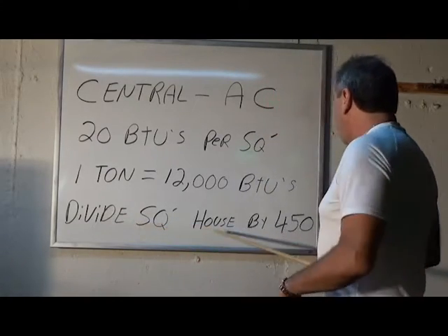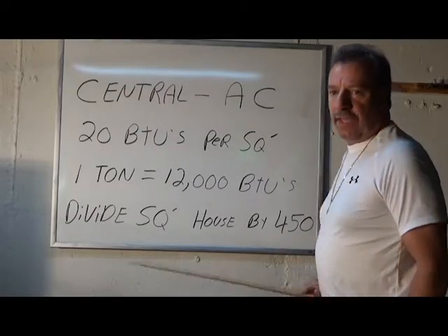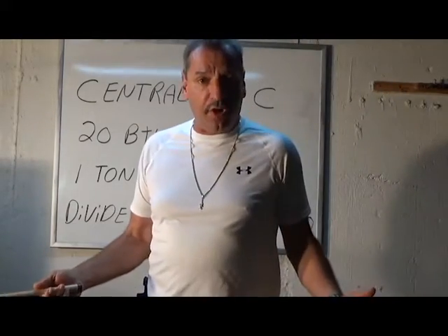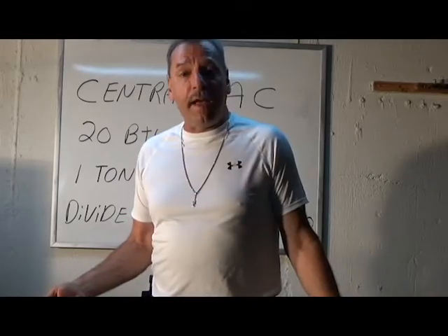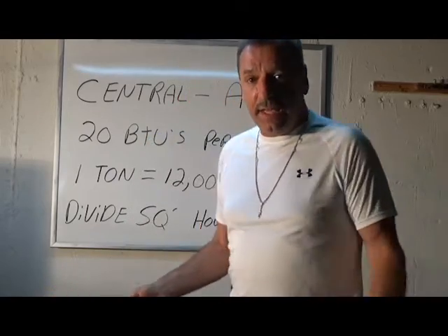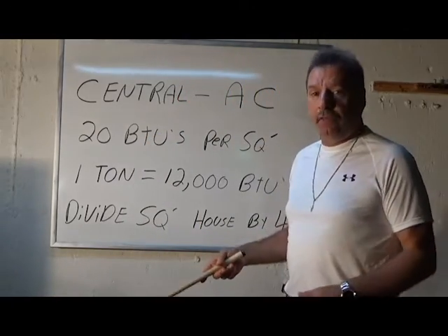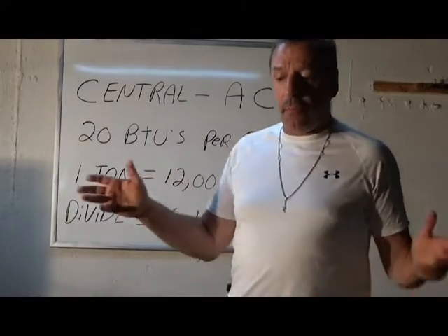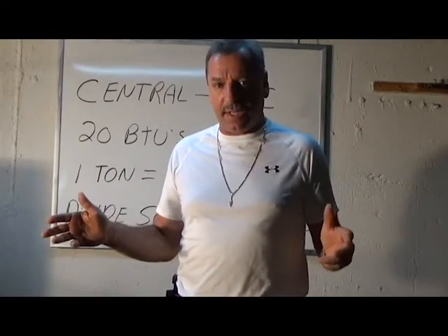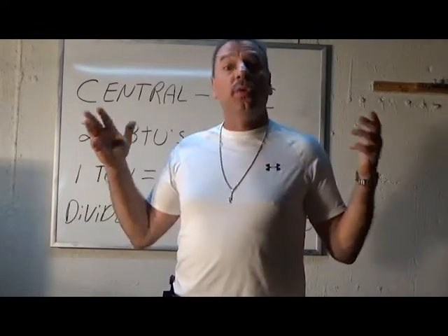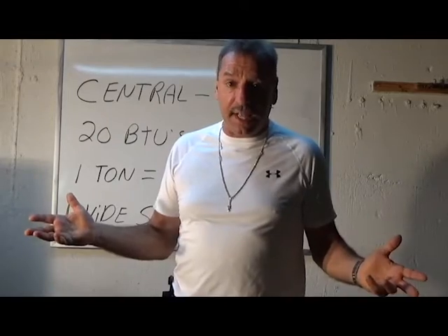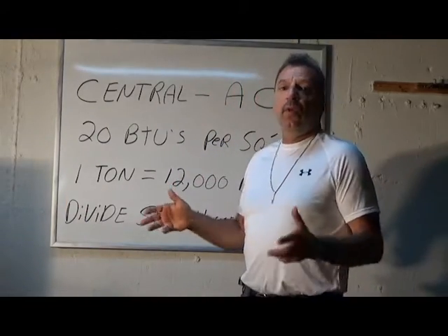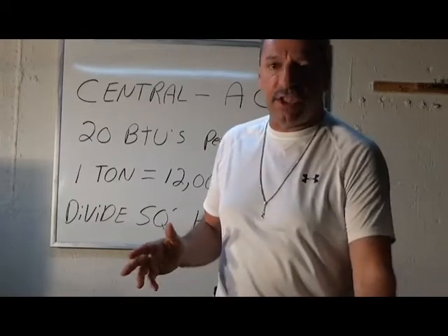You divide the square footage of the house by 450. For instance, if you have a 2,000 square foot home and you divide it by 450, you would come up with 4.4 — that's the tonnage you would need. They don't make a 4.4 ton compressor or condenser, so you step up to a 5 ton condenser. So a 2,000 square foot home would take a 5 ton condenser.